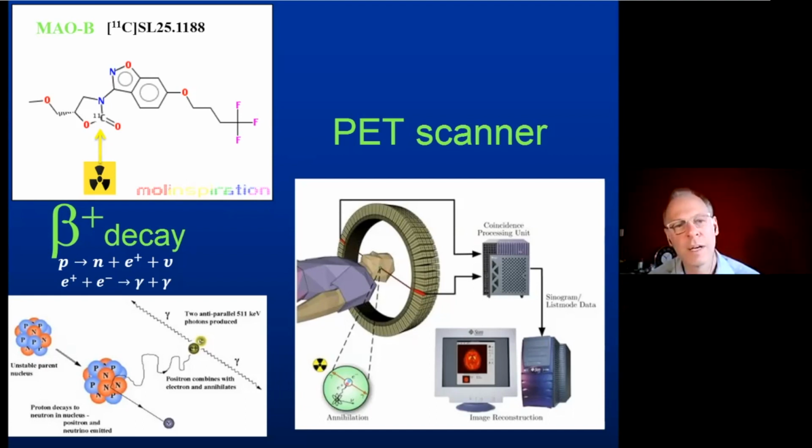And the PET scanner doesn't measure, even when PET means positron emission tomography, the PET scanner doesn't measure positrons. Actually, the PET scanner measures the gamma rays that are generated from the annihilation of the positron with an electron in the area. So along 1 or 2 hours that we acquire the PET image, there are millions of these gamma rays detected in the PET scanner. And later, with some algorithm, we get an image that has in each element of volume a concentration or a number proportional to the activity in this area of the brain.